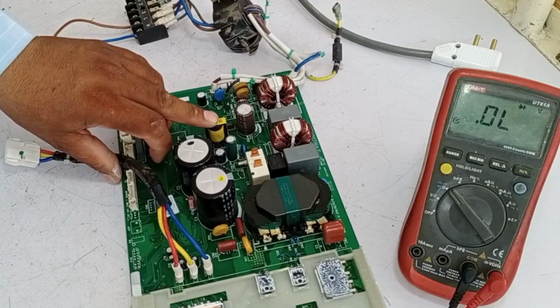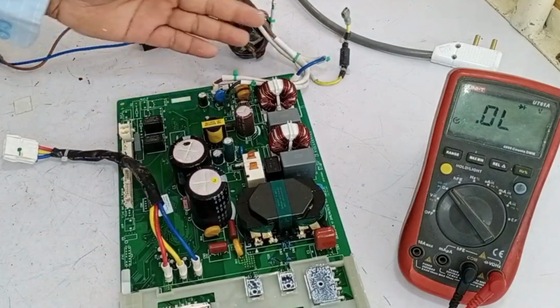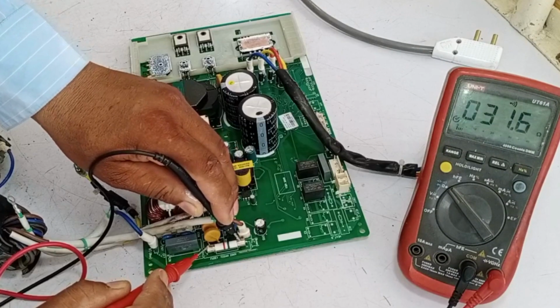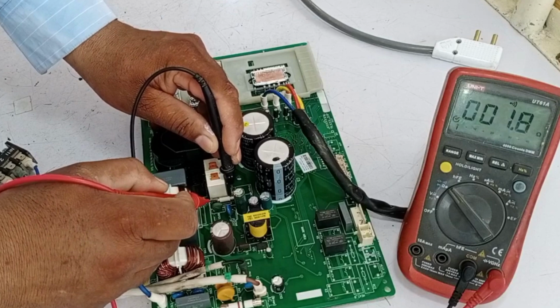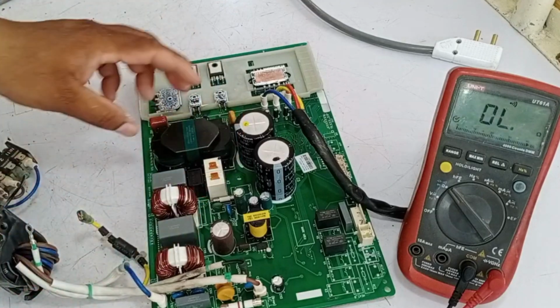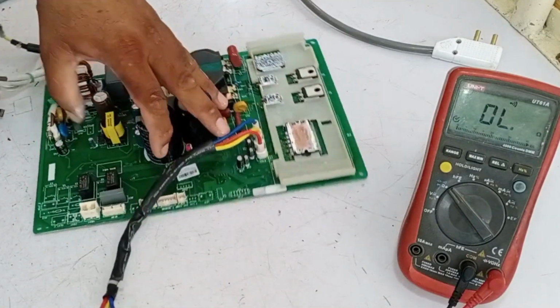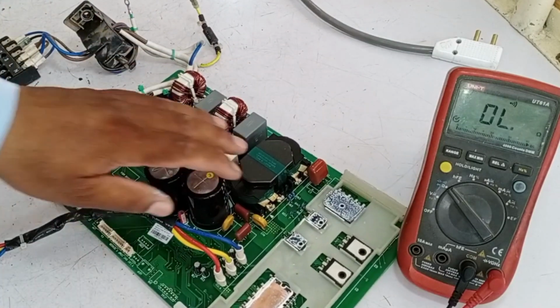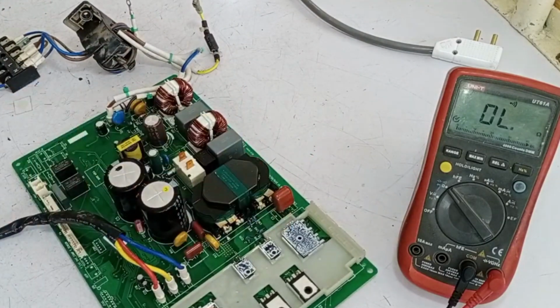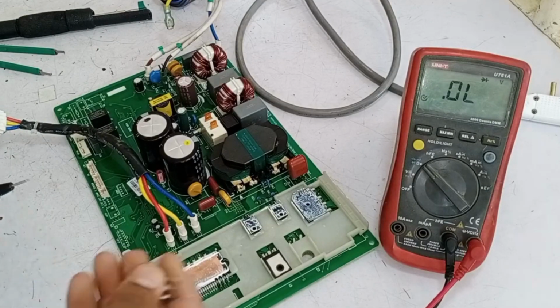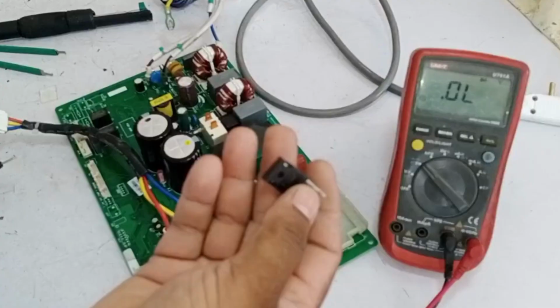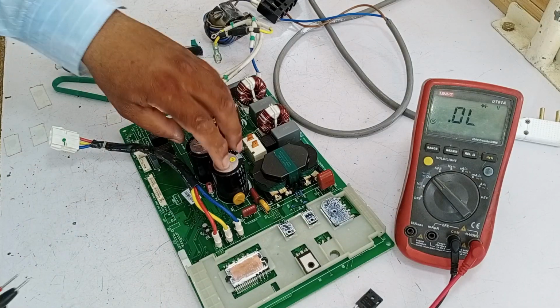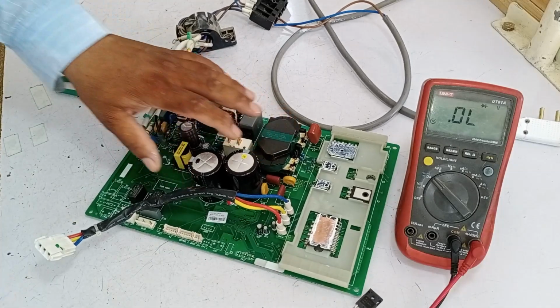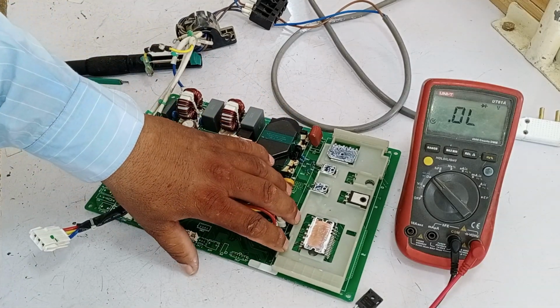When we inspect it physically, all the capacitors and components appear fine. I also checked both fuses, and they're both intact, with no issues present at this time. So, we've identified the fault, and now we'll see if replacing it fixes the PCB. After that, we'll recheck the bridge rectifier and verify all voltages again to ensure everything is functioning correctly. I've now removed the IGBT from the PCB, and I'll test it separately to show you. First, I'll explain the current position, as the IGBT wasn't showing accurate readings, and the rectifier was also faulty.